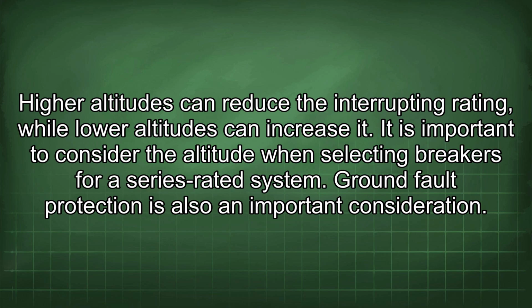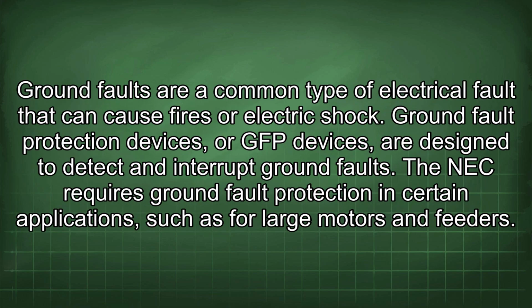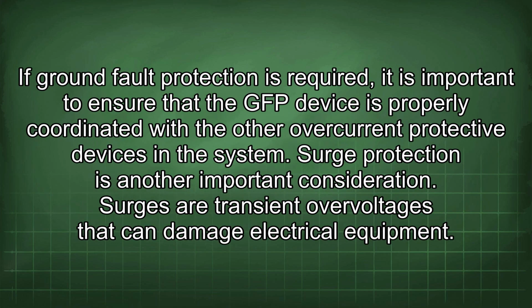Ground fault protection is also an important consideration. Ground faults are a common type of electrical fault that can cause fires or electric shock. Ground fault protection devices, or GFP devices, are designed to detect and interrupt ground faults. The NEC requires ground fault protection in certain applications, such as for large motors and feeders. If ground fault protection is required, it is important to ensure that the GFP device is properly coordinated with the other overcurrent protective devices in the system.